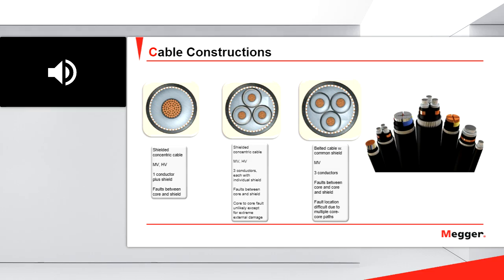This last cable construction is very typical in paper insulated cables. So when we have paper insulated cables with a common shield, we need to be aware that the fault could happen between the phases and the concentric, but also between the phases themselves.